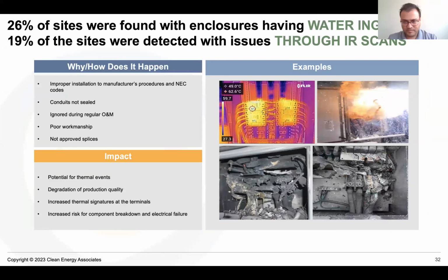From the previous slides, we found 26% of the sites, that is 26 out of 100, having water ingress into the enclosures. These enclosures can be AC combiner panels or inverters, and the water intrusion can be due to a bad or damaged gasket, or a screw missing over the enclosure.